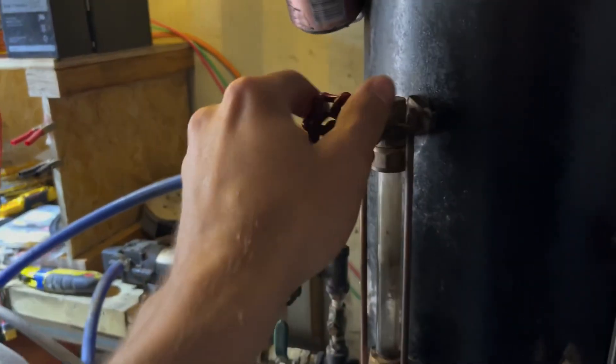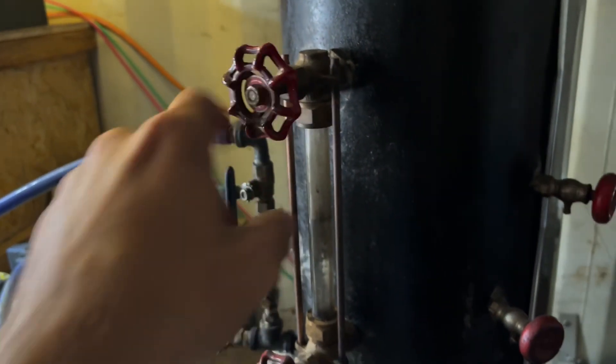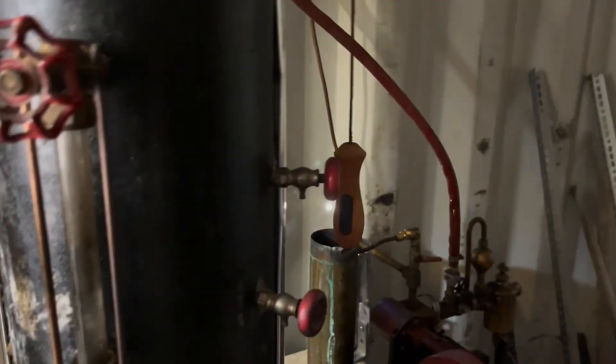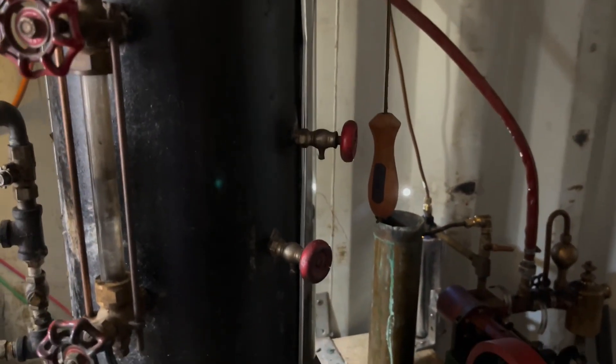In the event that this gets cracked, you know, you shut these off top and bottom and you're onto your tricocks. That way you can tell where your steam is. One of them will produce steam. Like right now, the water level's about with the upper tricock. You can have more of these. I just have two. Two's about the minimum.